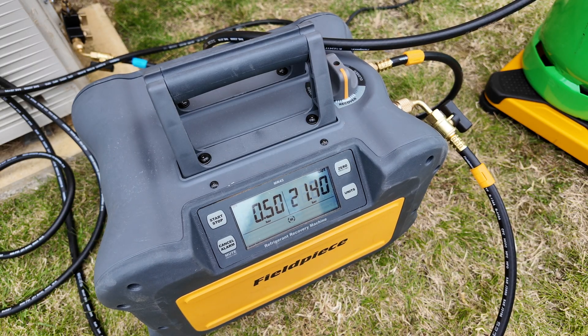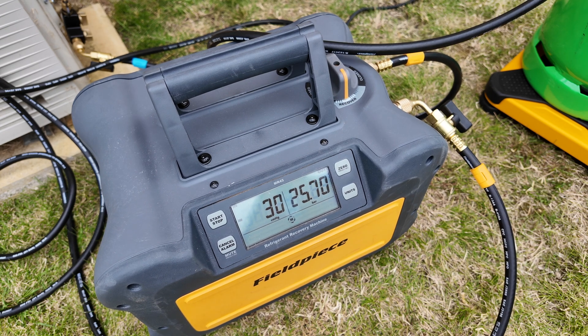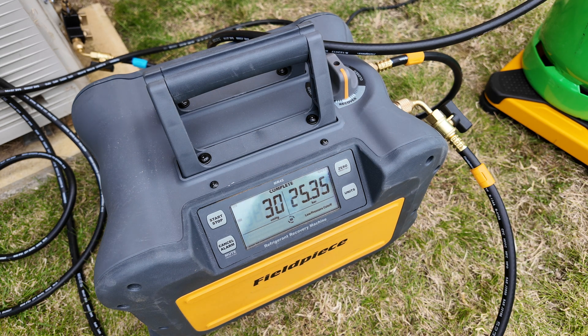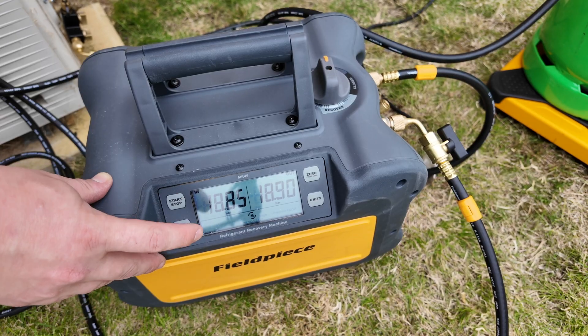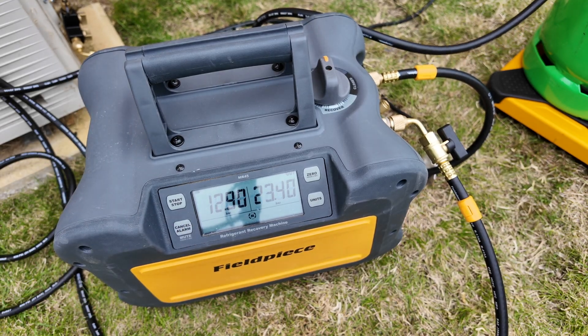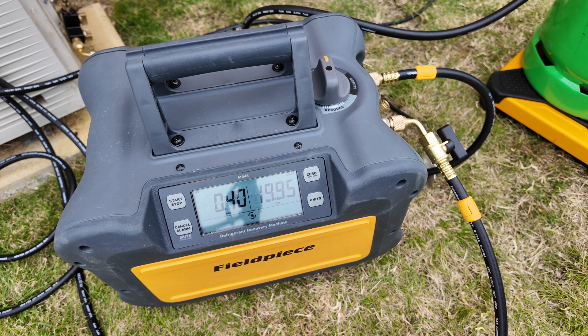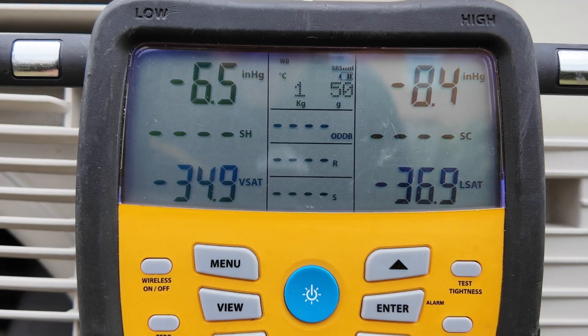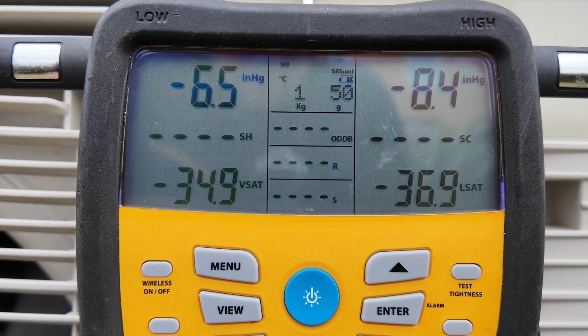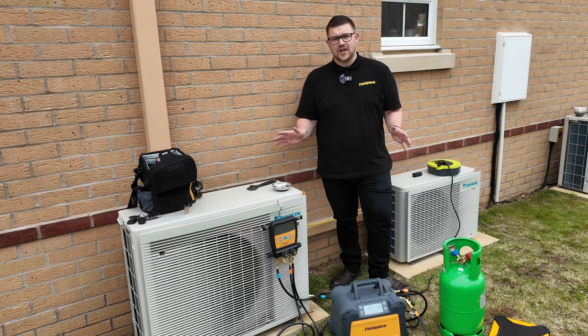Once the machine has completed the recovery it will go into a small negative pressure to help draw any remaining refrigerant out of the system, and then the machine will cut off automatically and sound an alarm to signify the completion of recovery. Now I can mute this alarm and set the dial to the self-purge position and press the start button to ensure that all of the refrigerant is cleared from the machine into the cylinder. Once this is complete I can check the final recovered refrigerant value, which in this case is 1.05 kilograms. That's how to carry out a system recovery using the Fieldpiece tools.